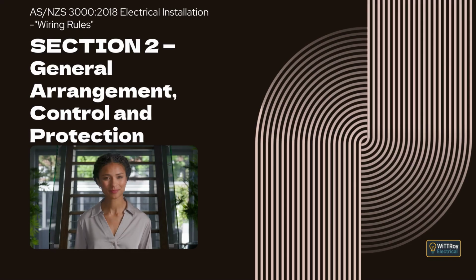In New Zealand, AFDD protection is required for any final subcircuit rated at 20 amps or less when it supplies locations with a higher fire risk. These include places where flammable or combustible materials are processed or stored, such as farm sheds, woodworking shops or storage areas, places containing irreplaceable items, historic buildings built from flammable materials, and school dormitories where socket outlets supply student areas. In these locations, wiring faults can lead to fire, so the standard requires an AFDD to be installed at the switchboard that feeds these subcircuits. The notes explain that if the wiring is in poor condition, such as circuits passing through high-risk areas, AFDD protection is strongly advised even if it is not strictly required.